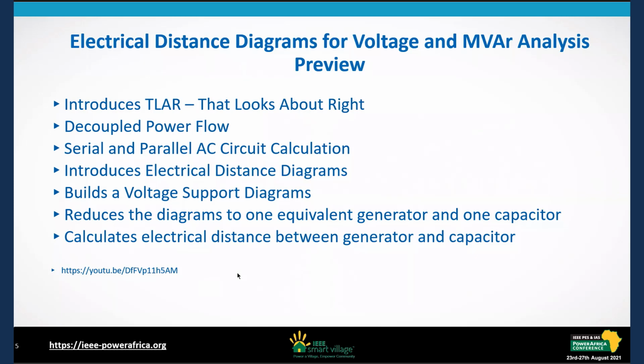Then you'll be looking at voltage support diagrams, how to describe a diagram with all the generators that provide voltage and megavar support for a given bus. And having voltage support diagrams is becoming more and more critical. We're replacing synchronous generators with renewable inverter-based devices, and they don't provide the level of voltage support and voltage strength that those synchronous machines really do provide.